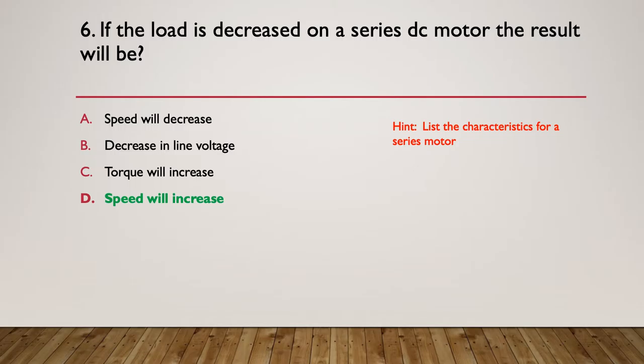So series motors are very well known for their speed will increase. To get grunt and any use out of a series motor, you've got to keep the load well and truly on it. If you lightly load it, it will increase its speed considerably.